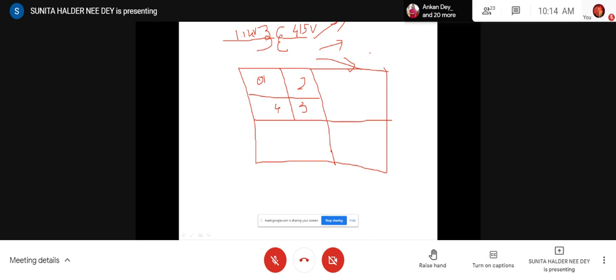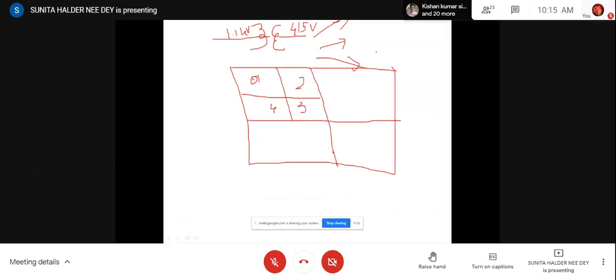Then what will be the power? For power calculation, we need to know what power is required to be supplied. Now, what is required to be supplied we have already got, say for the last D group, I have seen 1123 point something or 1126 point something, but that is the connected load. So the demand factor is generally no more than 1 but near 0.8 or 0.9. So it is better to estimate the maximum demand at first, then we find out the capacity of the transformer. Have you understood what I have told?